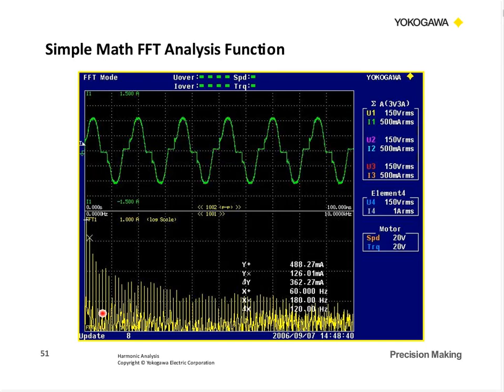They're due to the point that this is not a true integer number of cycles. And so the simple FFT just takes all this data, calculates point by point, and we have an odd number of samples, and it looks at maybe that last half cycle or partial cycle, and it gets confused. It thinks it's harmonics, and that's what's reported down here.